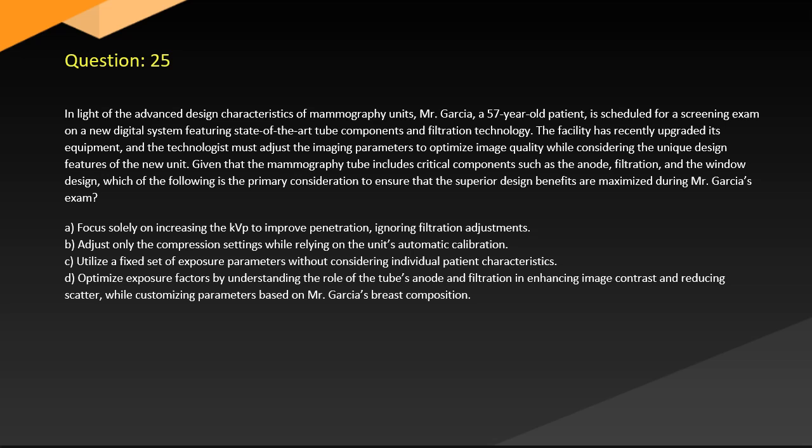A. Focus solely on increasing the kVp to improve penetration, ignoring filtration adjustments. B. Adjust only the compression settings while relying on the unit's automatic calibration. C. Utilize a fixed set of exposure parameters without considering individual patient characteristics. D. Optimize exposure factors by understanding the role of the tube's anode and filtration in enhancing image contrast and reducing scatter, customizing parameters based on Mr. Garcia's breast composition.